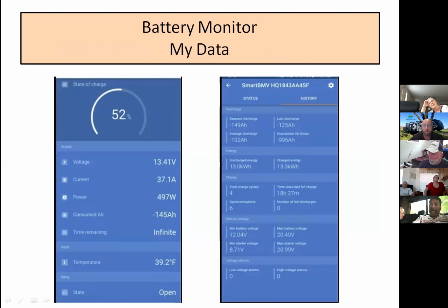This is actual data from my phone, from the BMV 712 meter feeding information via Bluetooth, captured last January at the Quartzsite rally out in Arizona. At the time, my battery bank was at 52% state of charge, with 13.41 volts from the battery bank. The current was positive 37.1 amps, meaning the solar charging system was turned on and I was using less power than I was putting back into the batteries, by 37.1 amps. The power was positive 497 watts. I had consumed 145 amp hours since the batteries were previously charged. Since I'm putting power back into the batteries, I have an infinite time until they are discharged.